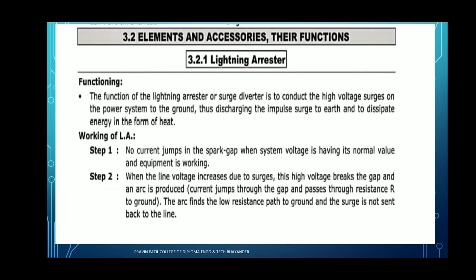And the lightning arrestor is the device. The function of the lightning arrestor or surge arrestor is to conduct the high voltage surge on the power system to the ground, thus discharging the impulse surge to the earth and dissipating the power in the form of heat. This is the main function of the lightning arresters used in power systems.